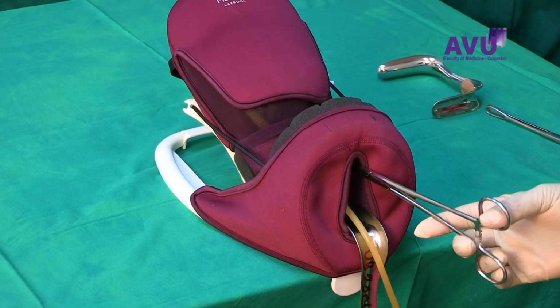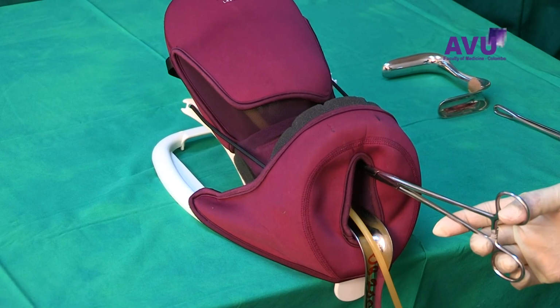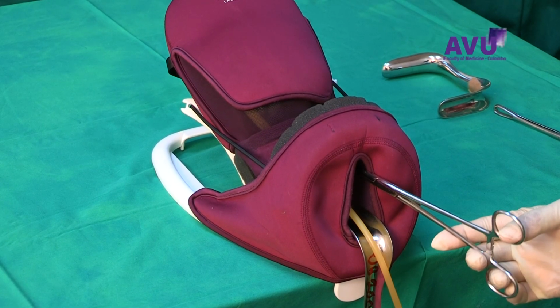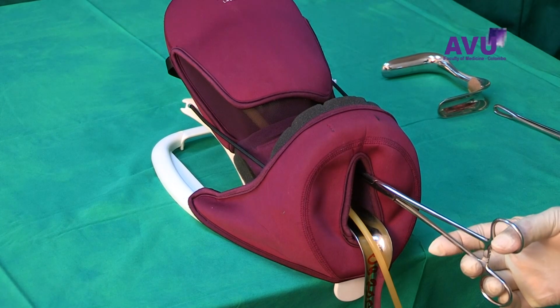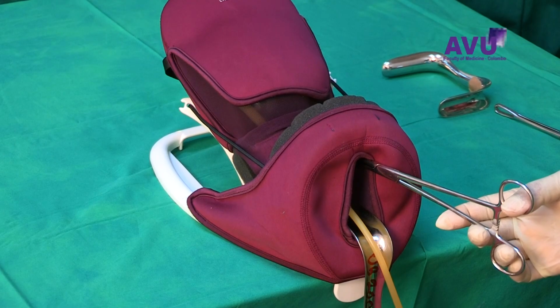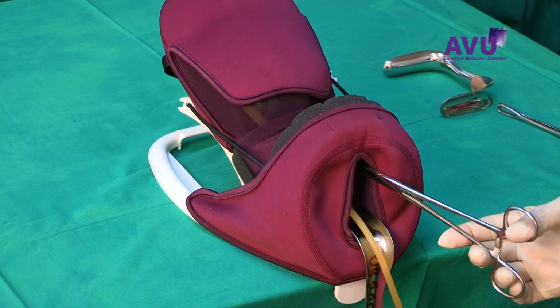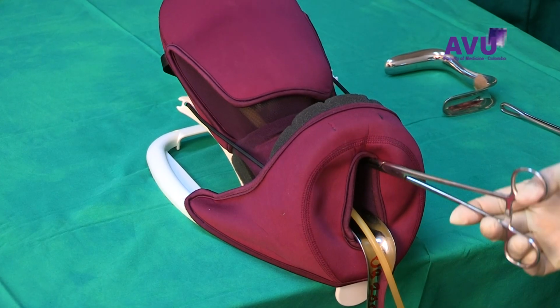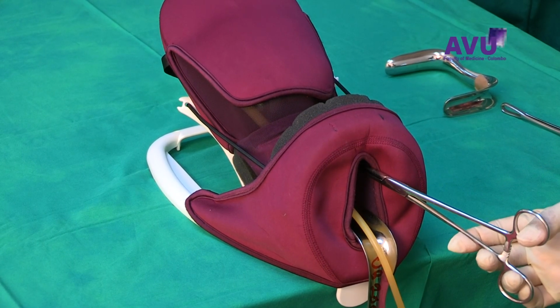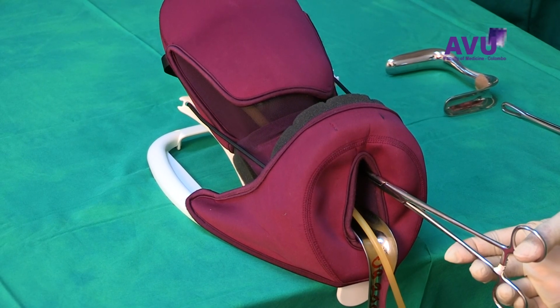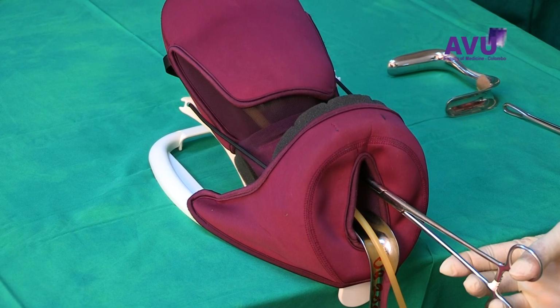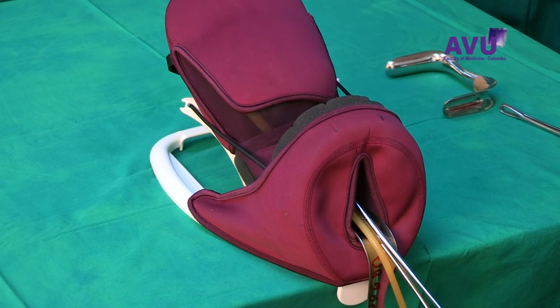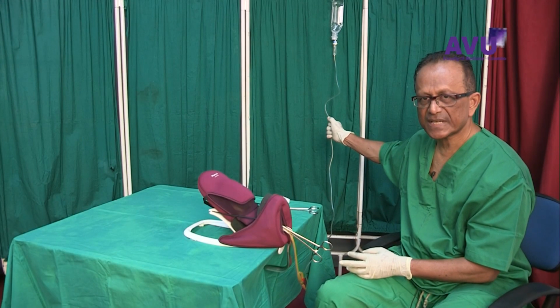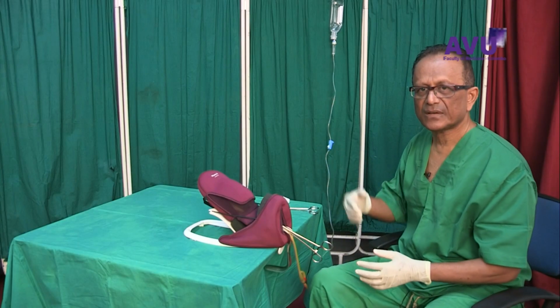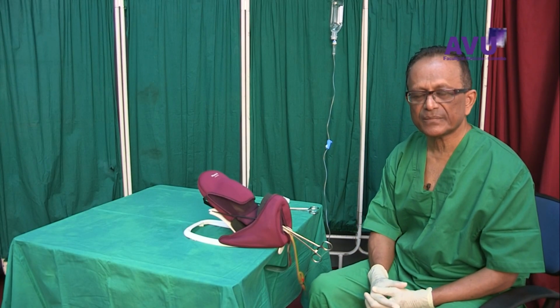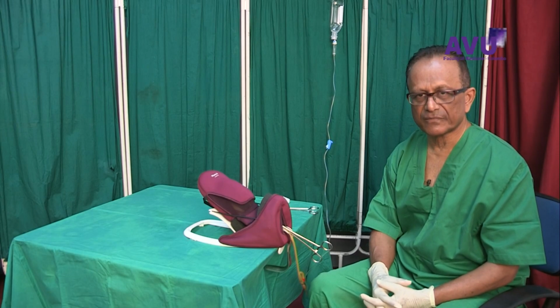As you can see, now the condom is getting filled with saline under passive pressure provided by the bottle. While this is happening, it is vitally important that you keep observing the cervix to see if you could see the balloon protruding out of it. Now, that is an important point in this procedure. When that point is reached, it indicates that the balloon might get expelled from the uterus at any point. At that point, we would need to close the tap of the giving set. Usually this point is reached when about 350 milliliters of saline has been filled into the balloon.